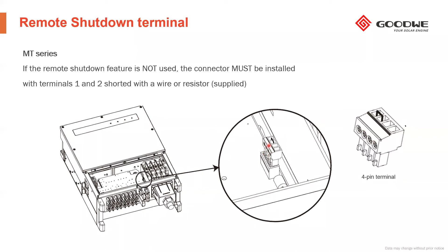Let's go with the commissioning. Before the commissioning, we want to show this slide because we've seen during the last year, while preparing the GoodWe Plus program and this kind of presentation, and also based on our after-sales experience, that the installation of inverters is often done by a different team from the commissioning one. That means there may be two teams, or a team for installation and one person for commissioning. But what I want to highlight is that the person or team responsible for carrying out the commissioning must ensure that the installation has been done properly—and that's very important, as is everything we've covered previously in the manual and the slides.